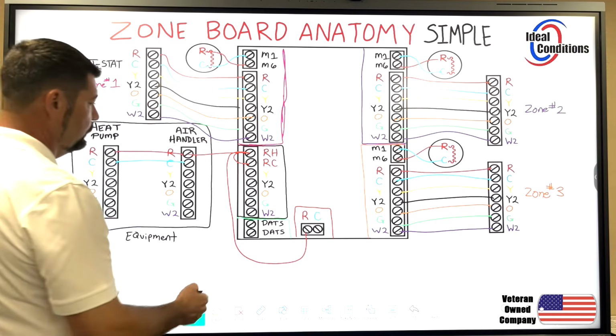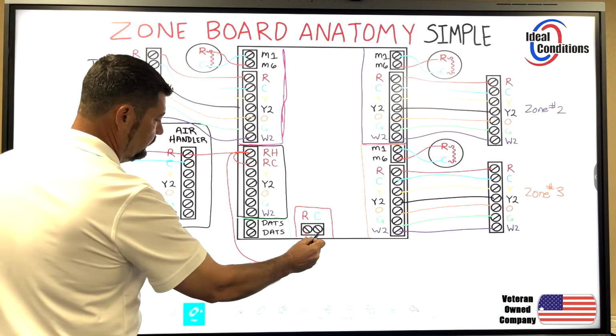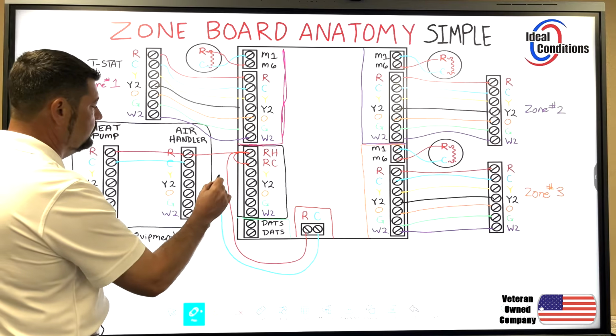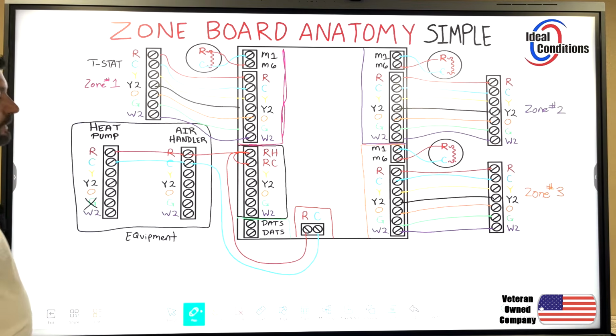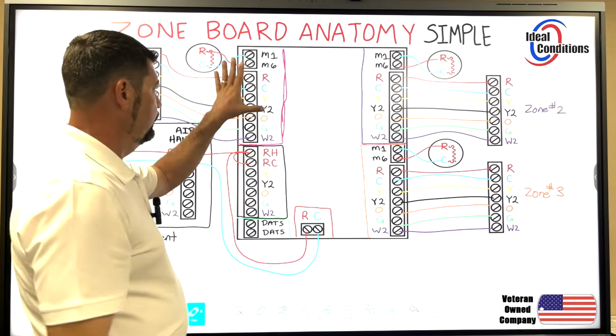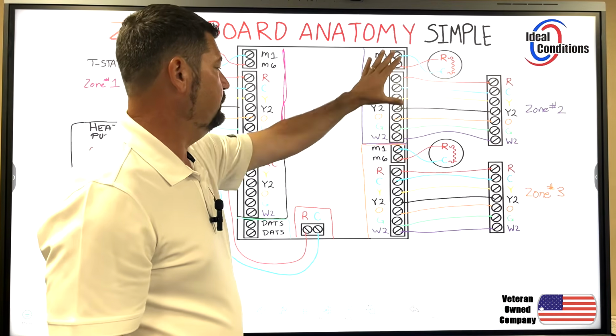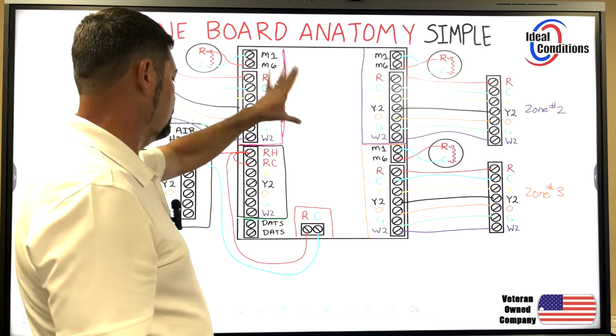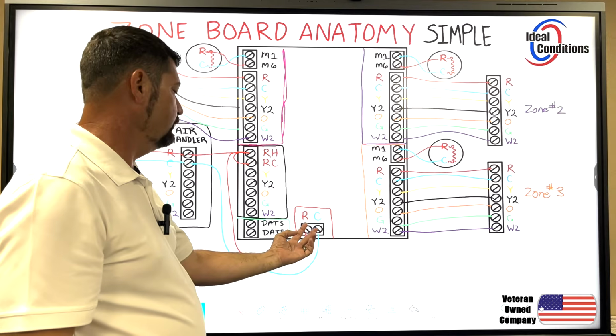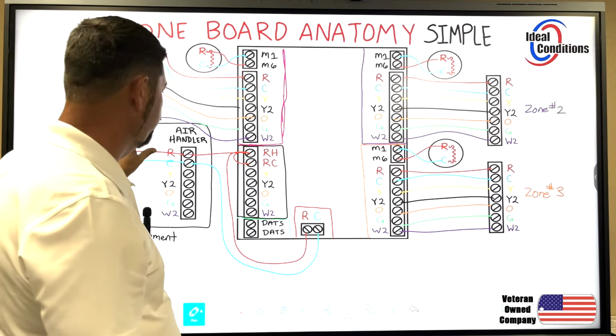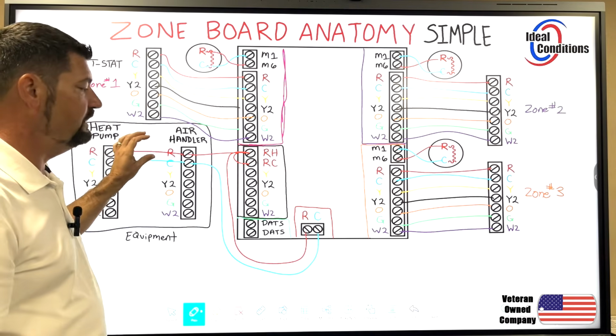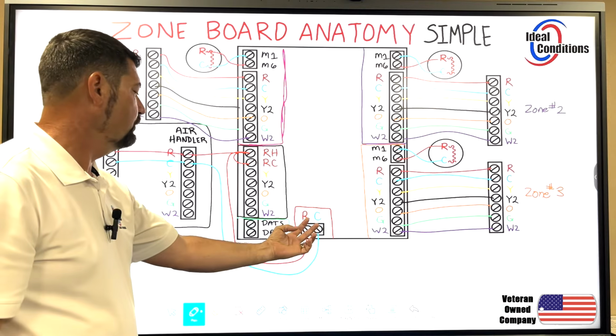This gets powered from the transformer inside the air handler, the equipment itself, and the common comes back up. Now these three thermostats and three dampers can operate because we applied 24 volts from the primary 75 VA transformer to the board.